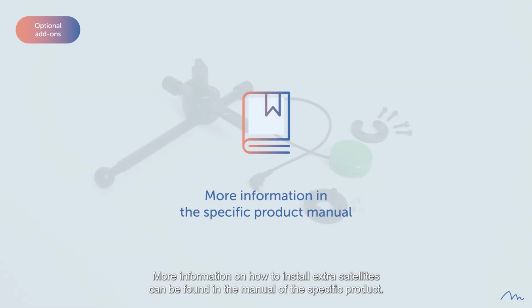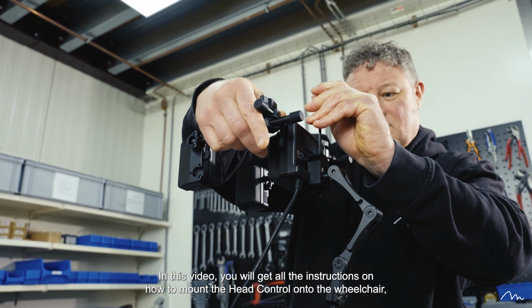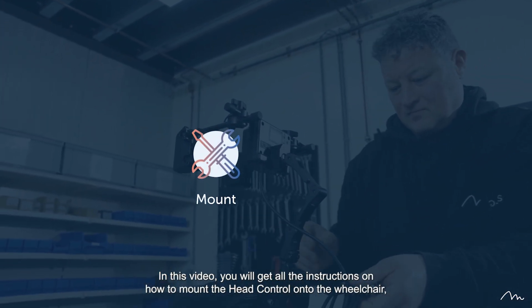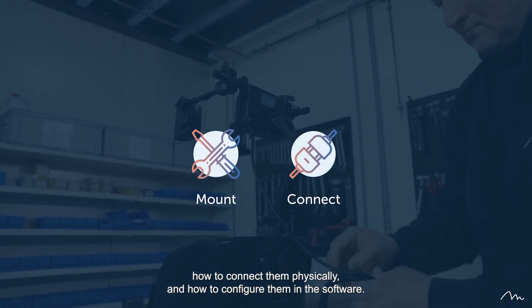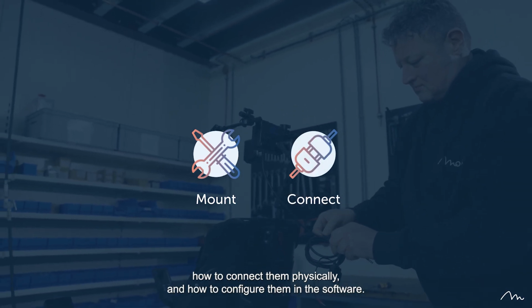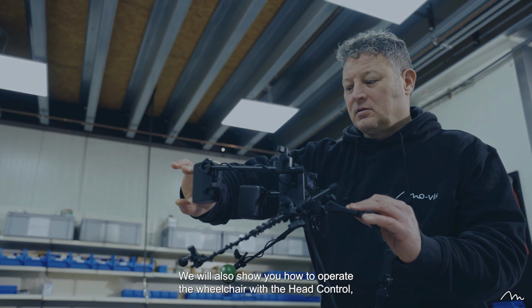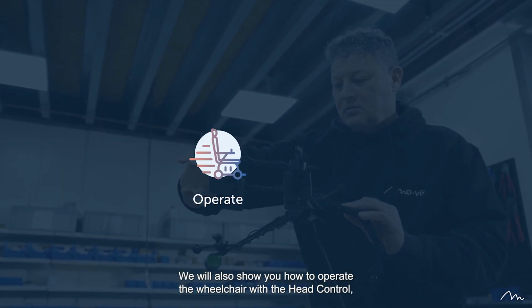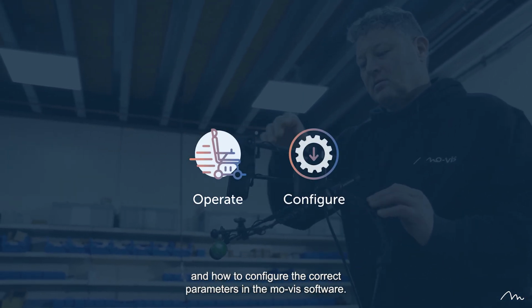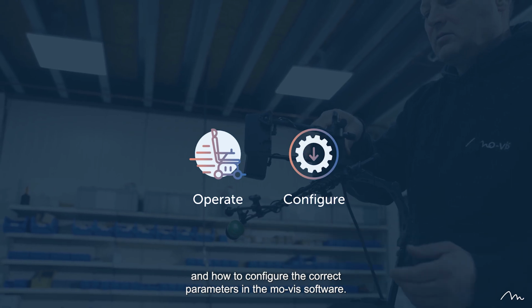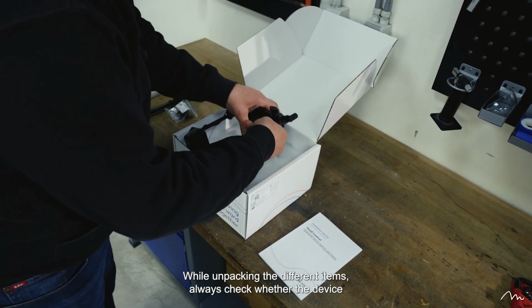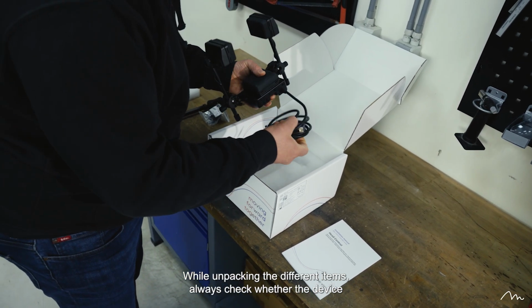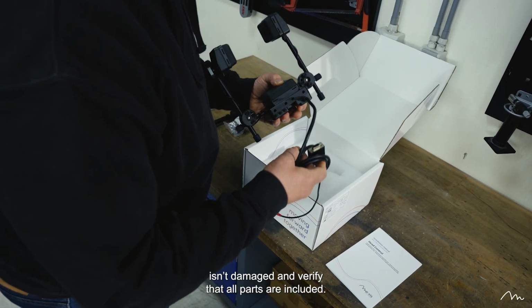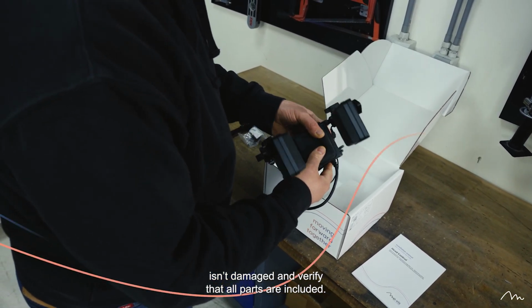More information on how to install extra satellites can be found in the manual of the specific product. In this video, you will get all the instructions on how to mount the head control onto the wheelchair, how to connect them physically, and how to configure them in the software. We will also show you how to operate the wheelchair with the head control and how to configure the correct parameters in the mo-vis software. While unpacking the different items, always check whether the device isn't damaged and verify that all parts are included.